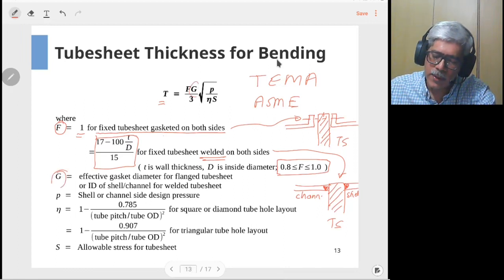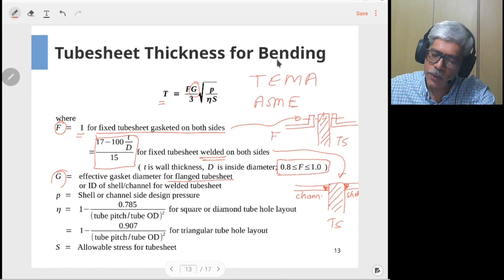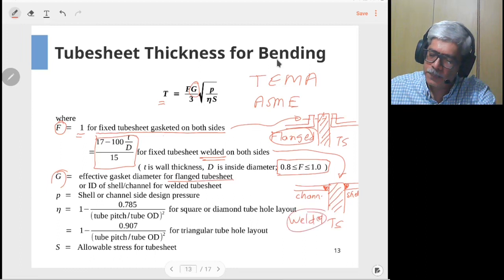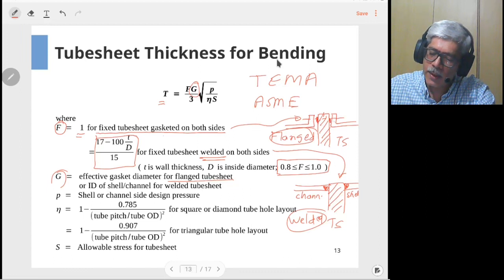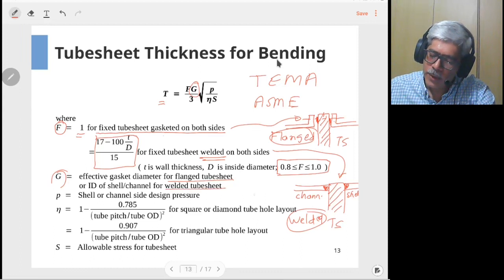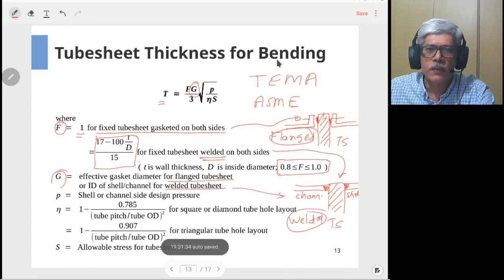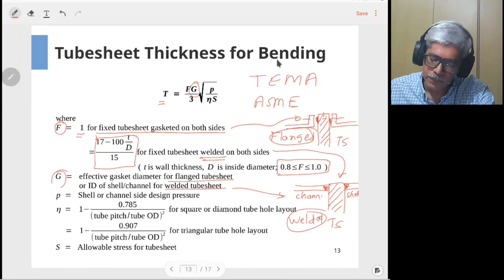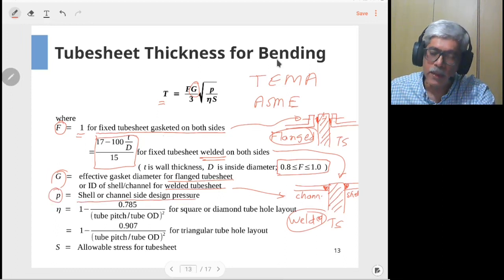The next parameter is G, the effective diameter. For a flanged tube sheet, G is the effective gasket diameter — the diameter of the gasket placed at the joint. For a welded tube sheet, G is the inside diameter of the shell or channel, whichever is larger, and that value is used for the calculations.